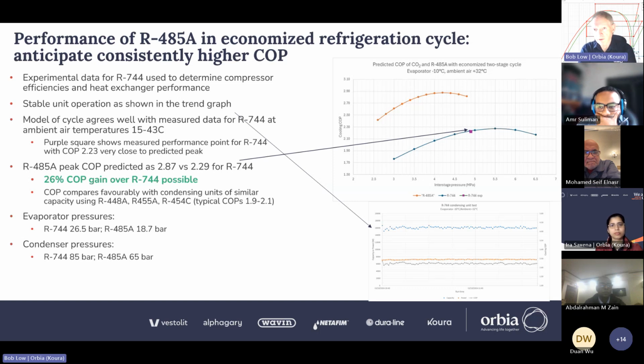The top graph on this slide shows the effect of interstage pressure for the compression path on the COP of both refrigerants. So CO2 here is in blue, and the blend is the orange curve. And you can see the peak for the blend is about 2.9 COP with an interstage pressure of just over 40 bars. The peak for the CO2 is 2.3 at an interstage pressure of about 55 bars. In fact, the unit control, when we let it run for the baseline, had the interstage pressure slightly lower than that, at about 48 bars. And I think that's because the unit's designed to work over a range of conditions, and so the optimum strategy isn't necessarily to go for the absolute peak COP at this condition. But it's only 2.2 versus 2.3, so it's basically almost identical COP at that rating point. And the purple square on that graph shows our measured data, and it sits exactly on where our model sits. So we're comfortable the model is realistic.